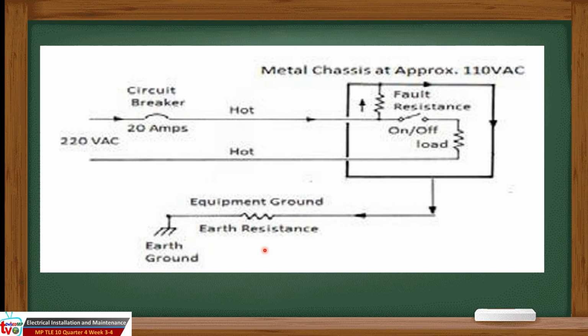If the fault resistance is more than 5.3 ohms, the circuit breaker will not trip off. However, the equipment grounding conductor will still hold the metal chassis to a safe voltage. More precisely, since the maximum fault current without the circuit breaker tripping is 20 amperes, the maximum voltage at the same chassis with respect to the ground is 20 times 0.2, which is equal to 4 volts.